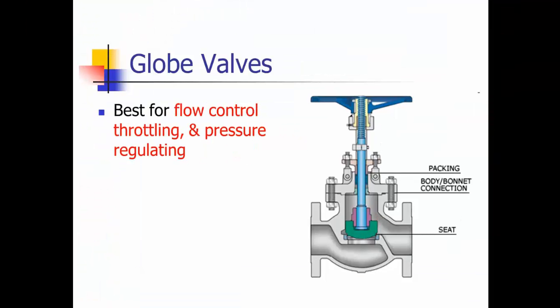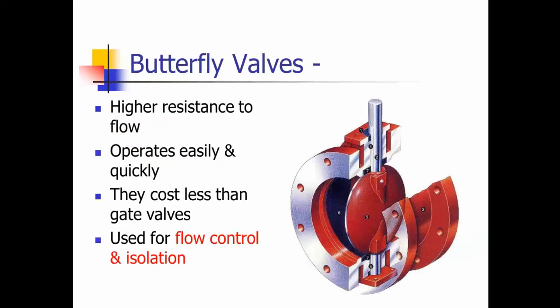Okay, this is the second portion of the operation and maintenance pre-certification test preparation. With the globe valves, we'll start up right from where we left. The globe valve is used for flow control. You can throttle it, and they're used in pressure regulating valves, this particular design. A butterfly valve, they also call them 90-degree valves because they're 90 degrees from full open to full close.